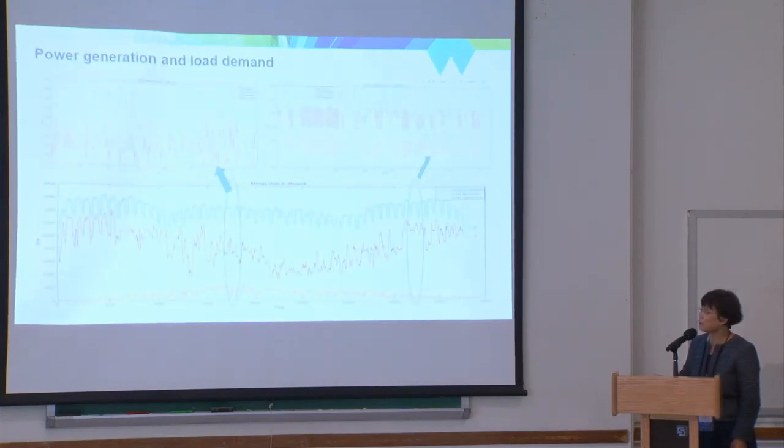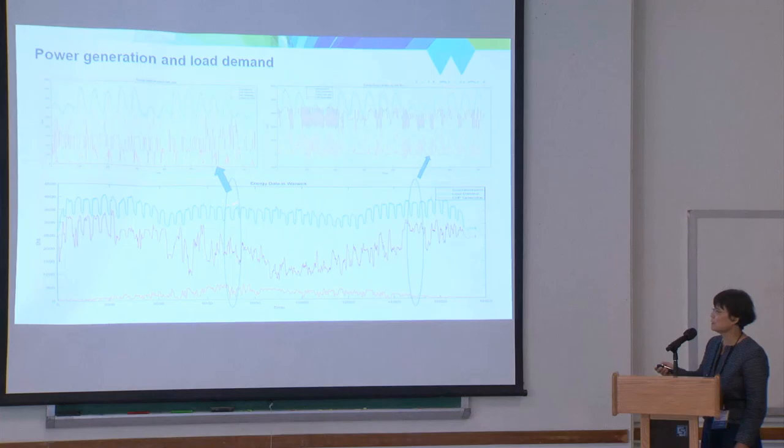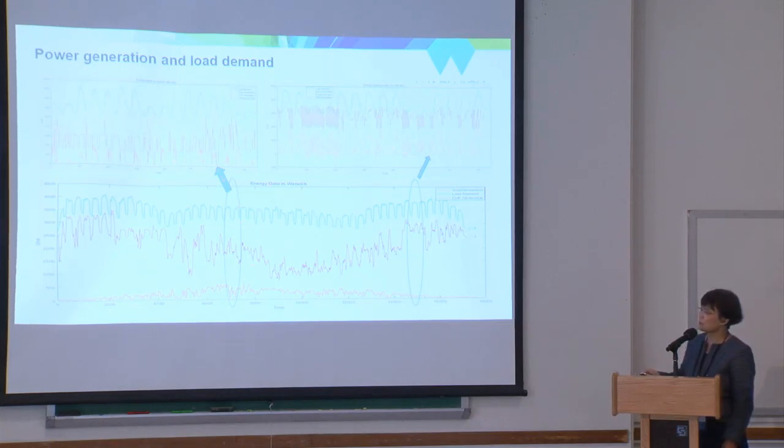Based on this design capacity we scaled up the whole-year solar generation. That's the curve for the whole year. We picked out two particular months — July and November. In both months, the solar generation is always in line with the blue line, which is the load demand. The purple line is CHP generation and the yellow is electricity bought from the grid. Below zero means we generate too much and just export to the grid for free. This means solar generation is in line with everything and we should be able to digest all the solar generation — we just need to check if it is economically viable.